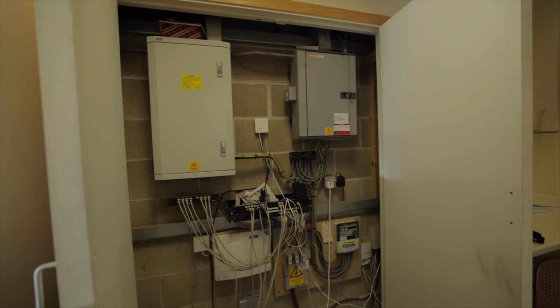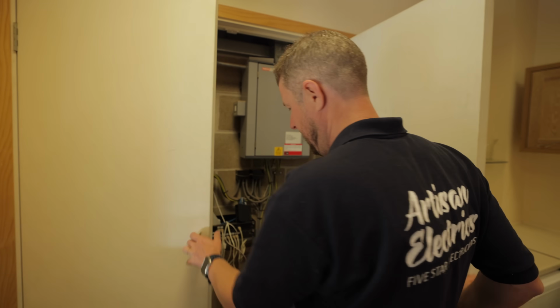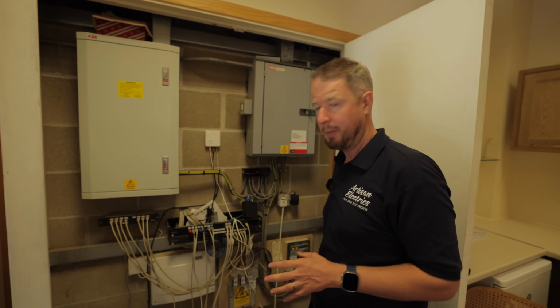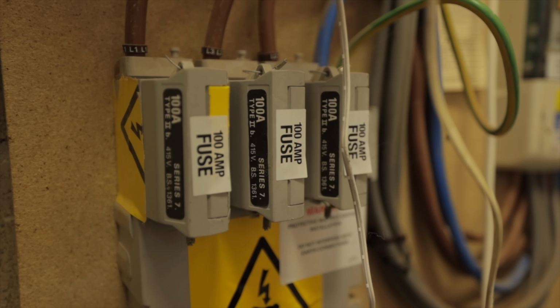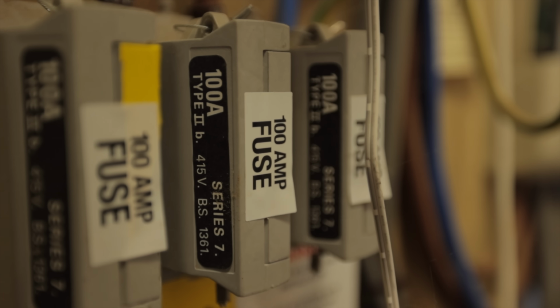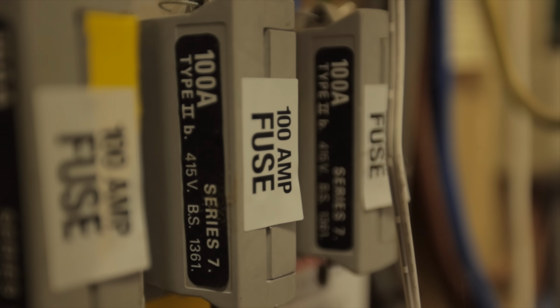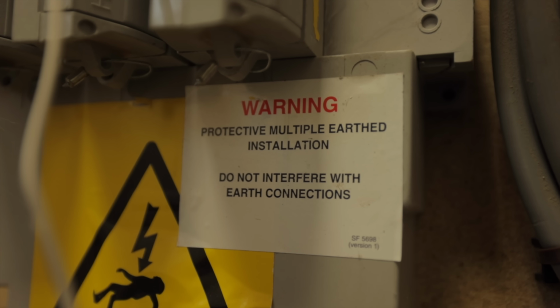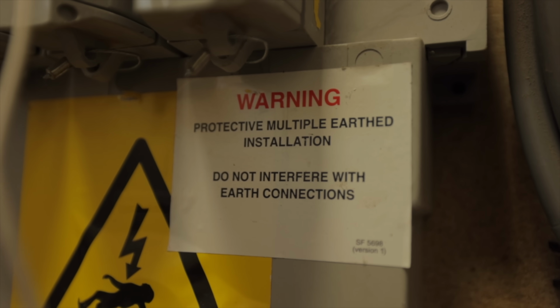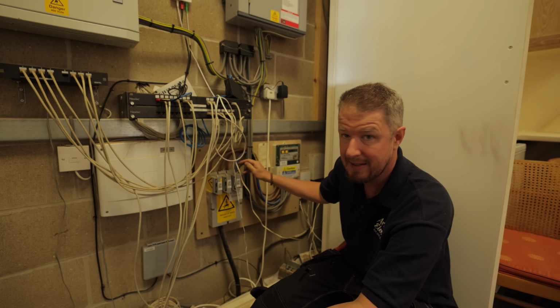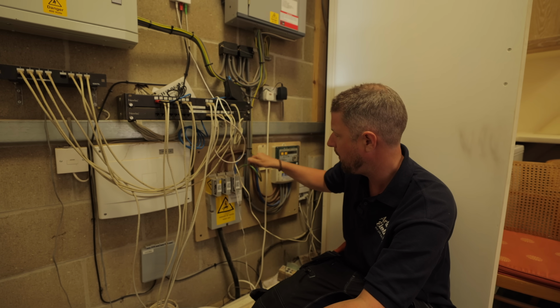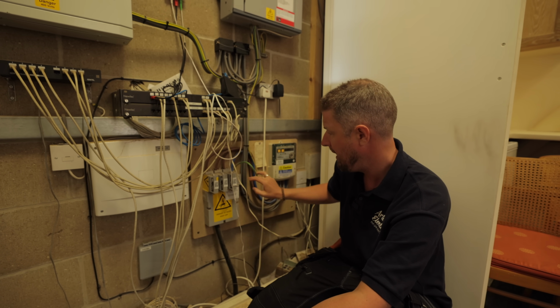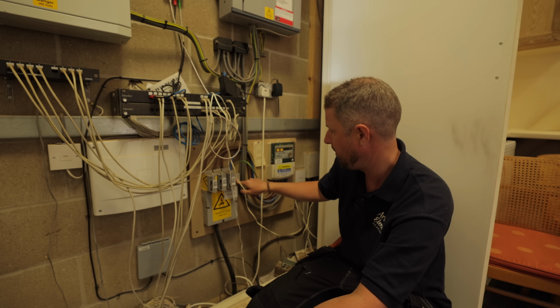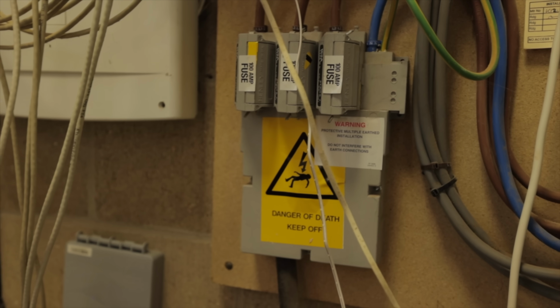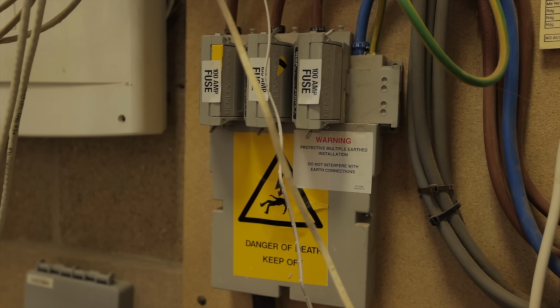So here's the main position, and the first thing we need to look at is the main incoming supply, which is here. We've got a 3-phase supply because we've got 3 main fuses here. On here there's a label saying warning, protective multiple earthed installation. So it's what we call a TNCS system, where the neutral and earth are combined. You can see that in this neutral block - the main earth comes off the neutral block. So that's a TNCS supply.